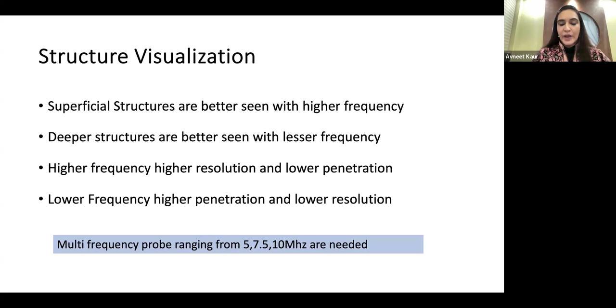Now, once we have chosen our organ, our preset, and which organs we want to evaluate, in the preset we can also choose whether we want to go for a term or a preterm neonate. You can talk to your engineer, and the engineer can easily create these presets in your machine, and based on that the machine can pick up the frequency. Suppose for a preterm baby I have a multi-frequency probe: for echo it can pick up 6 to 8 MHz, whereas for head ultrasound we can go 8 to 10 MHz for a term baby, and for a preterm baby the machine will pick up between 10 to 12 MHz for an extreme preterm baby, and for the slightly bigger ones it can pick up 8 to 10 MHz.